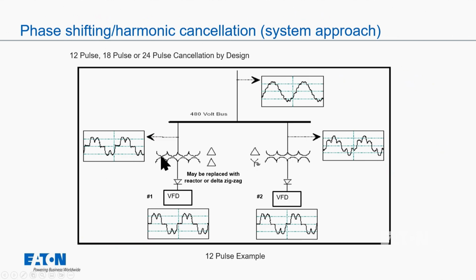Fifth and seventh, just like with VFDs, because these are 6-pulse drives, we could take fundamental, fifth, seventh, 11th, 13th, the fifth and seventh from this side cancel with the fifth and seventh from this side. So this could be a delta-delta, or could be a delta-zigzag harmonic mitigating transformer paired up with a delta-Y. And essentially you end up with two 6-pulse drives creating a 12-pulse system. And essentially if you think about what's going on here with this wave shape, that would be exactly the same as what we saw in the previous example once you eliminate the third harmonics.